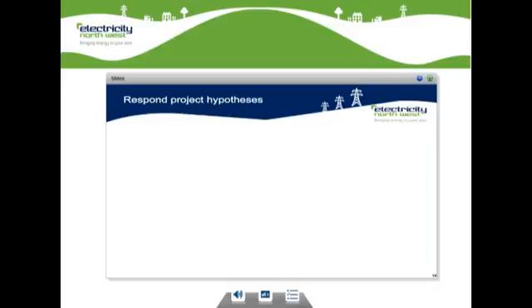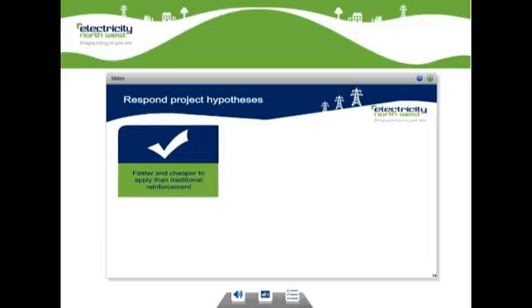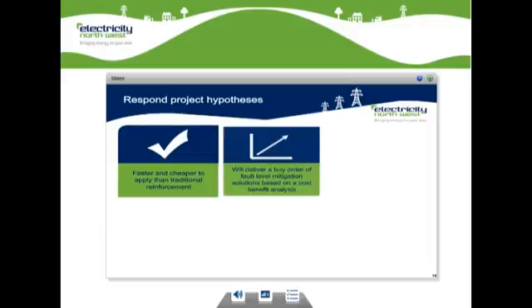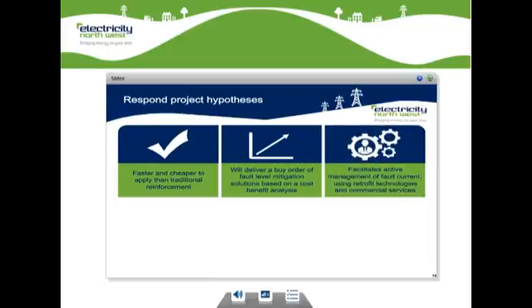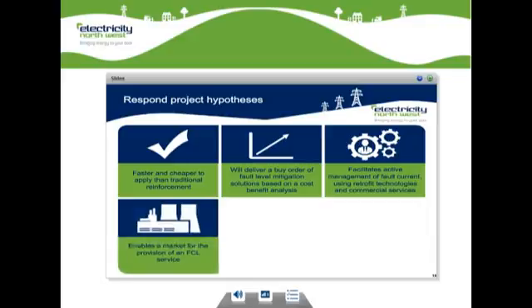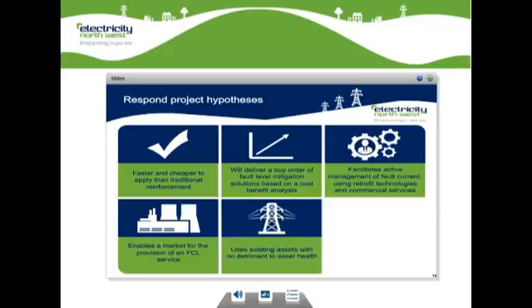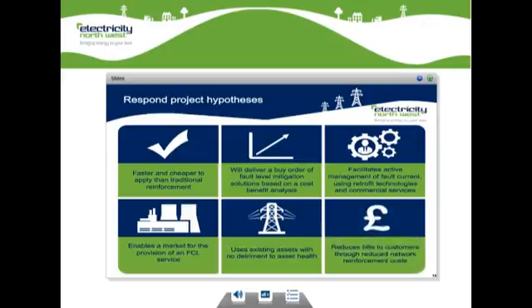So the hypotheses that we intend to prove during the project are that Respond, one, is faster and cheaper to apply than traditional reinforcement. It will deliver a buy order of fault level mitigation solutions based on a cost-benefit analysis. It will facilitate active management of fault current using retrofit technologies and commercial services. It will enable a market for the provision of fault current limiting services. It will use existing assets with no detriment to their health. And it will reduce bills for customers by reducing our network reinforcement costs.